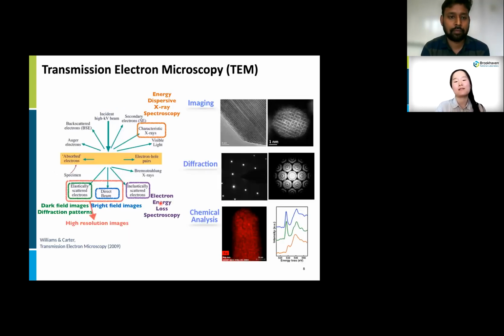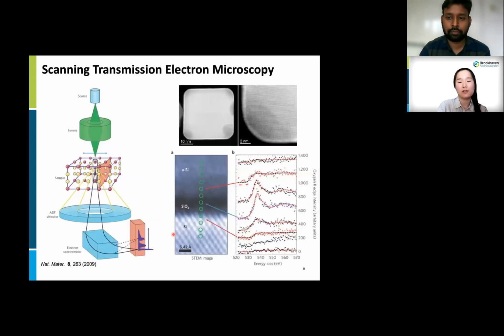When a high energy electron beam hits the sample, tons of signals come out. Using those signals, we can get images and electron diffraction patterns, and we can do chemical analysis with energy dispersive X-ray spectroscopy, EDX, or electron energy loss spectroscopy, EELS. In general, we use a parallel electron beam in TEM, but we can also make a small electron probe and scan the sample with it. We refer to this technique as scanning transmission electron microscopy, STEM. General TEM instruments offer both STEM and TEM operations. The beauty of STEM is we can do chemical analysis at atomic resolution. Here is an example of silicon oxide and amorphous silicon layers.